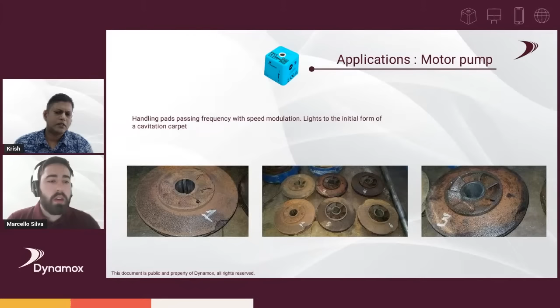Yes, Dynamox does not just sell hardware, as I was mentioning. That's a very good question. For motor pumps specifically, we can customize a full dashboard with automated detection of failures, the drive components, and the visualization you need for your pump. These smart dashboards are something we work on and can deliver for our customers to add value. With these pump dashboards, for example, you can see the differences in terms of the components, the drive, the motor, the cylinder itself, the assembly or the impeller, anything where you'd like to see the criticality of the equipment.